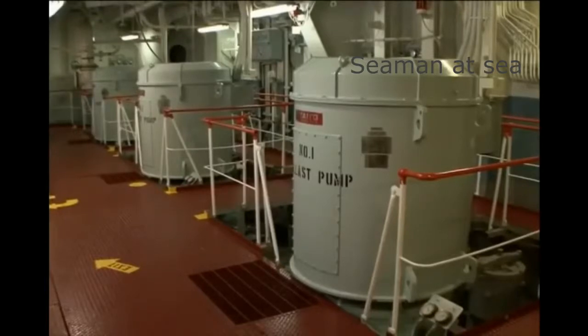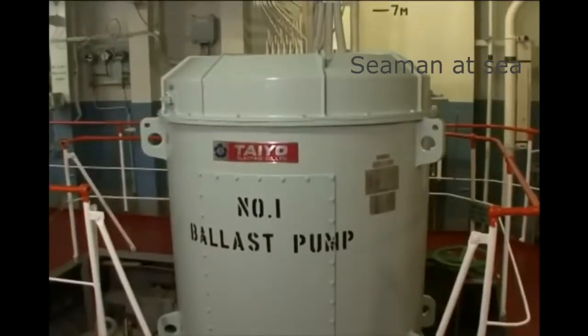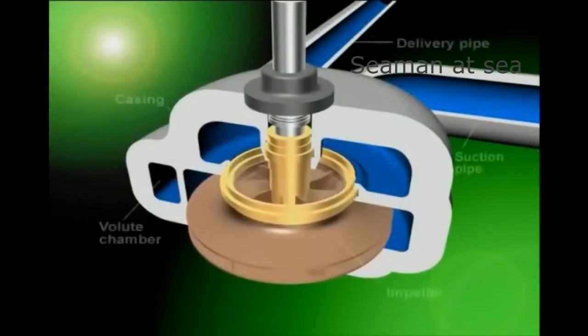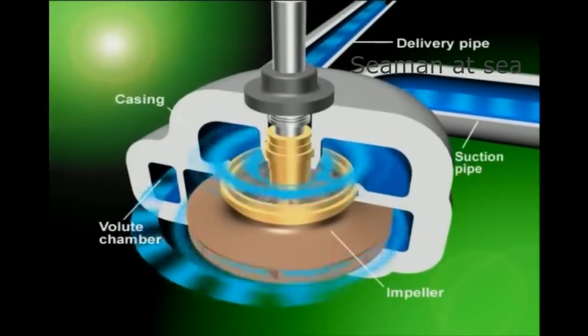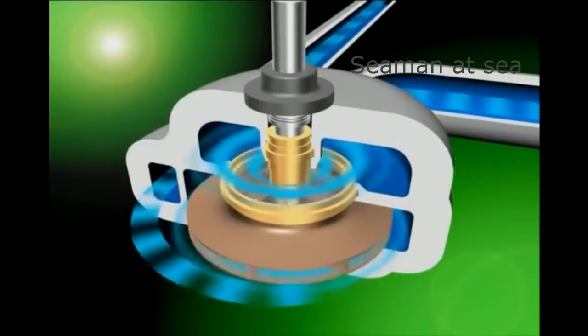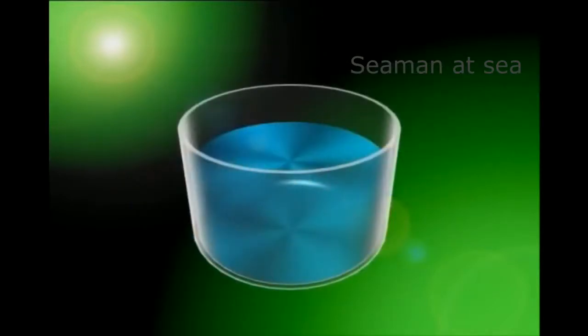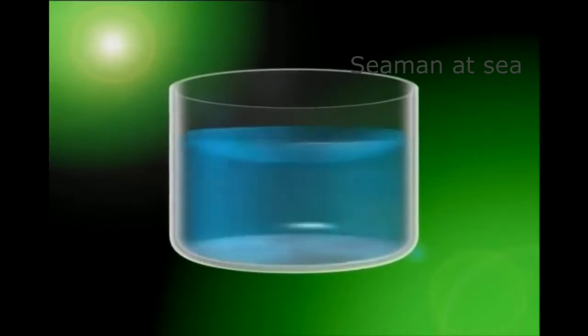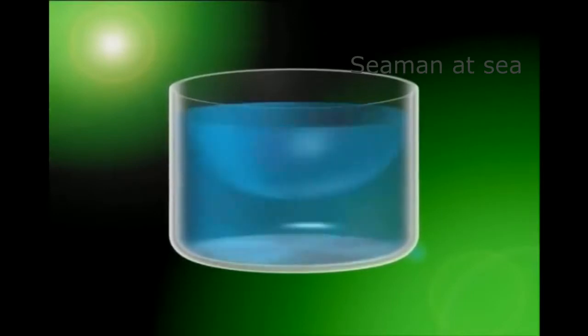There are various pump types. Of these, centrifugal pumps are commonly used in ship ballast operations. With centrifugal pumps, a motor is used to rotate a vane wheel called an impeller. The centrifugal force thus generated is used to send water out. To understand this principle: put some water in a cylindrical container and turn it around the container's axis. A centrifugal force works on the water and pushes it toward the container wall, making the water surface form a parabolic arch.